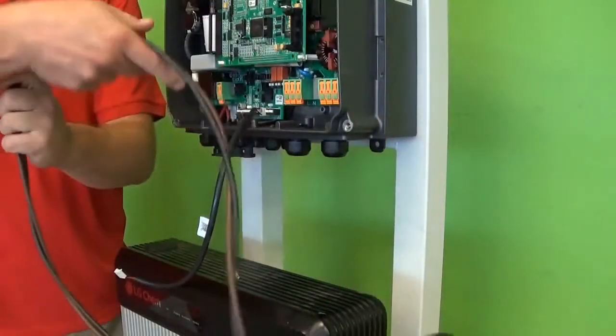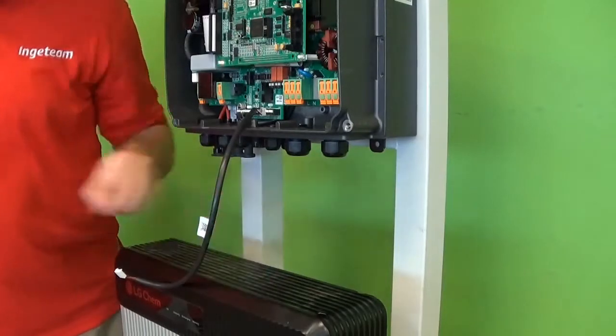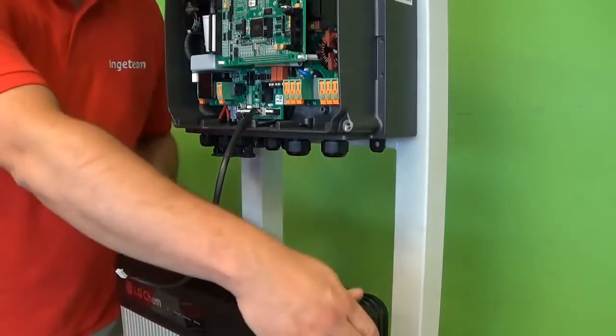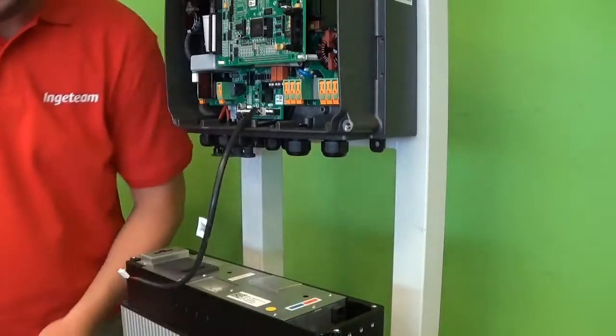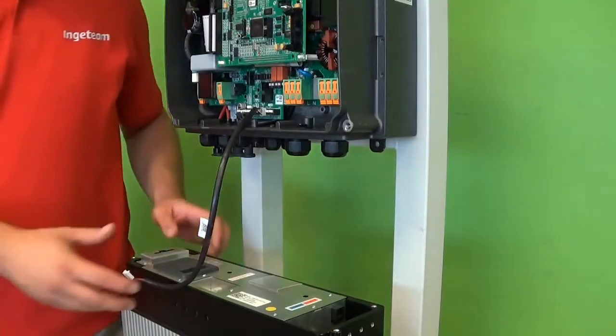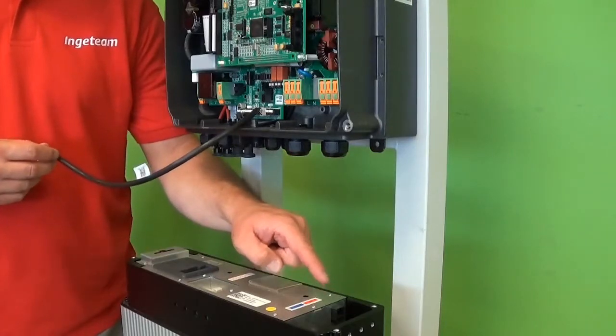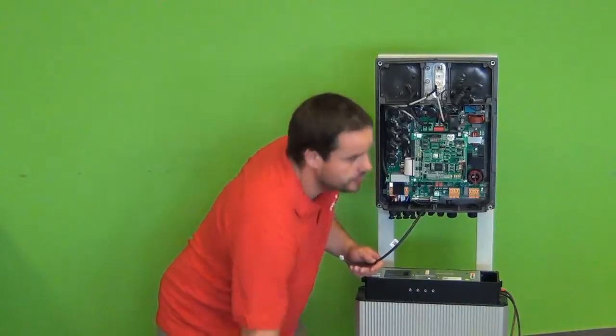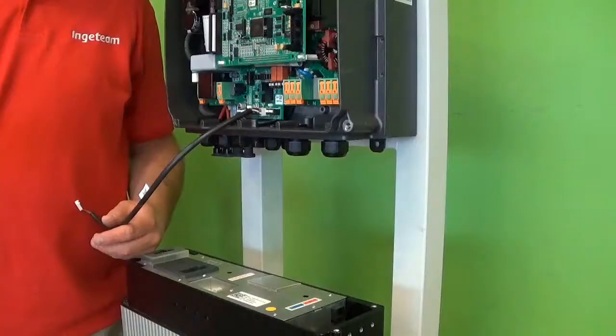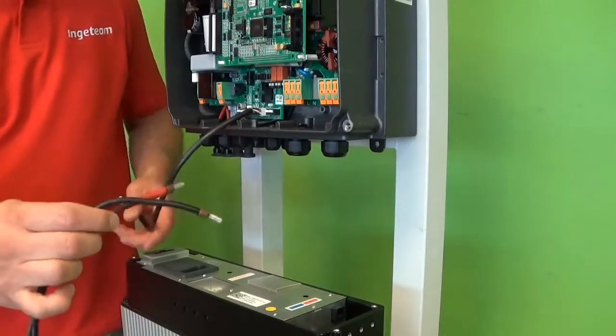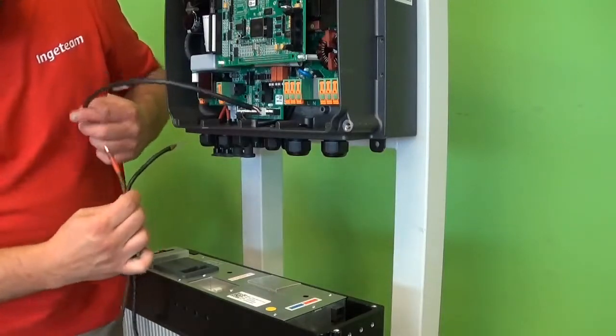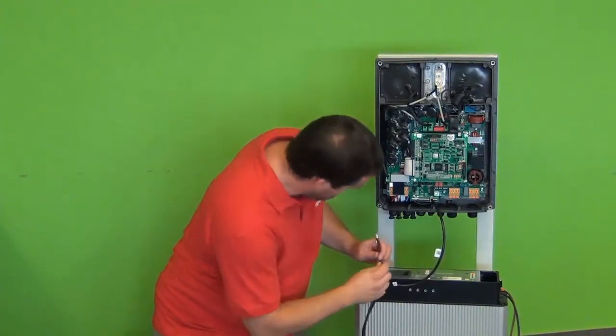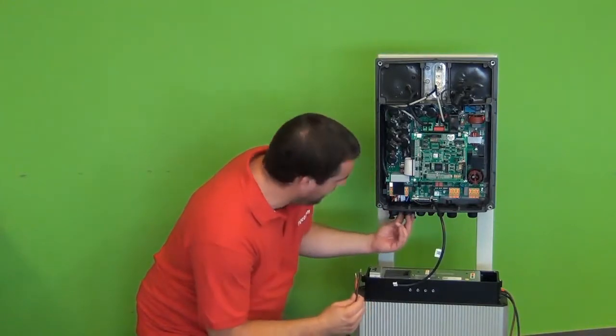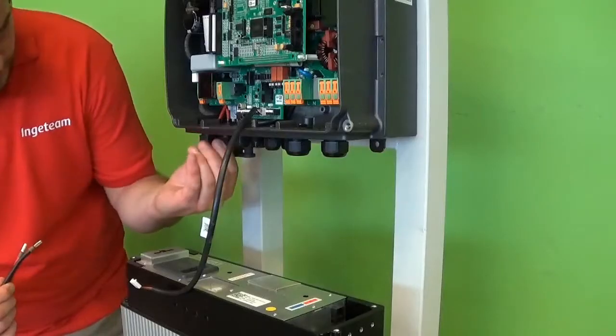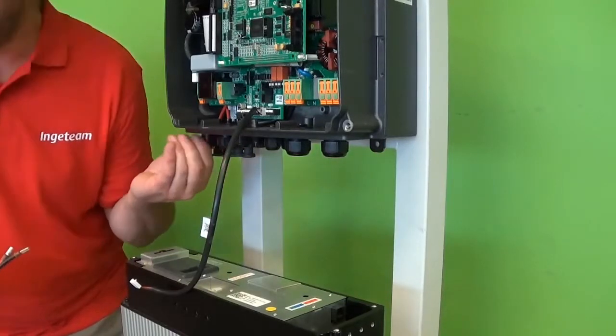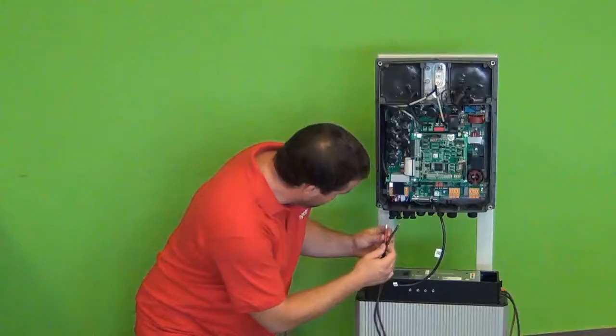connect the batteries. Okay, these batteries from LG here can be opened from the top. They have a cover that you can remove, and I have already connected the positive and the negative cable, these ones here, to the battery. All right, these 2 cables. So now these cables need to go into the inverter, right? To do so, there are cable glands over here at the bottom, and the only thing we have to do is to open them and to allow the cables to access into the inverter.